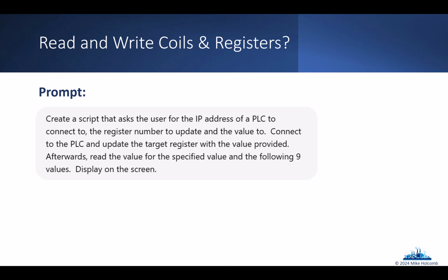Or if I look at the registers and I see a register that has a value of 72, that could be the set point for the temperature. Well, what if we can change those? Because Modbus is an unauthenticated protocol. It doesn't ask you for a username and password, or just a password, to be able to read those values and make changes. It just allows you to read those values and make changes.